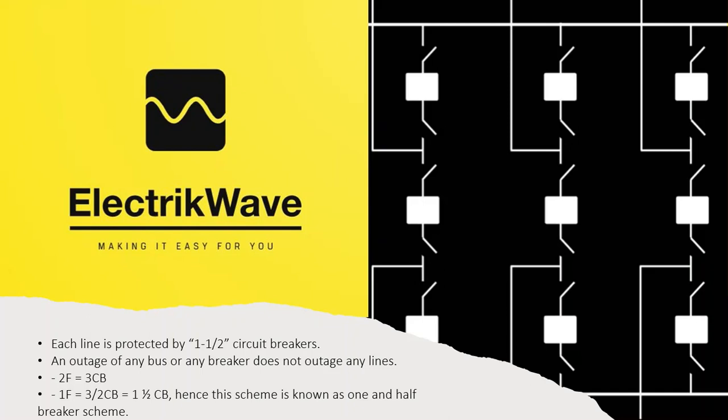Normally, both the bus bars are in service. This scheme has more operating flexibility than mesh bus. Requires 3 breakers for every 2 circuits. Widely used at high voltage, especially where multiple circuits exist, e.g. generating plants.